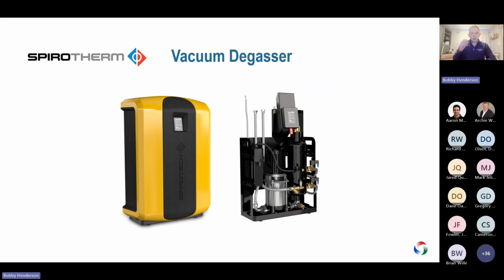Spirotherm, one unit I wanted, maybe everybody here might be familiar with their air and dirt separator offering. Spirotherm obviously produces a very effective air and dirt separator product, but this is a vacuum degasser. I've presented on this in the past, but this is basically if you need to remove 100% of your entrained air in a hydronic system, whether that's an industrial, process cooling, process heating, or comfort heating cooling. This is a really great product. You can treat up to, I believe it's 35,000 gallons of water with a single system. Relatively low cost, low intrusion. We can actually just use a couple 1-inch ports to plug into your hydronic system here and pull down over time 100% of your entrained air.